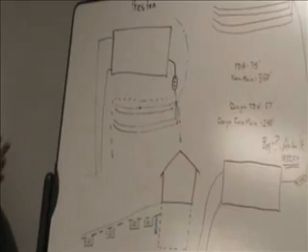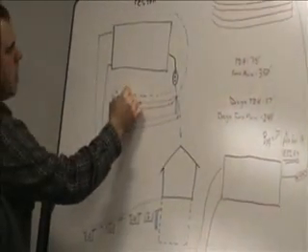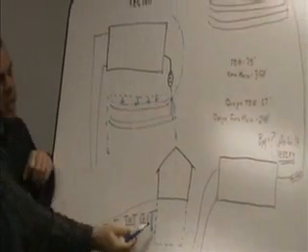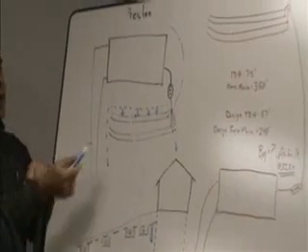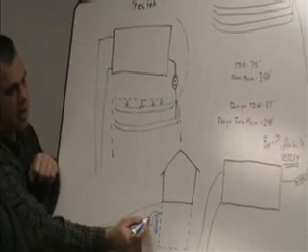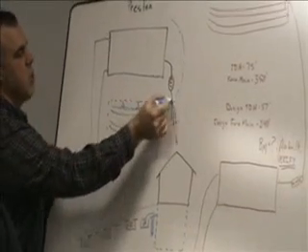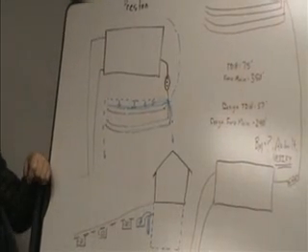We also thought maybe, and we're not entirely sure about this, that perhaps there's some hydraulic pressure on this line and maybe kind of acting like a curtain drain because it's the top line. This curtain drain's not picking up any of this stuff right here. So it may be acting as a curtain drain because it's shallower. And it might be just coming down into that trench right there. And then it's got enough hydraulic pressure, and we looked at the elevations. There's enough elevation there that it actually can work back through that multi-zone valve and down here. That could be happening. We're not entirely sure.